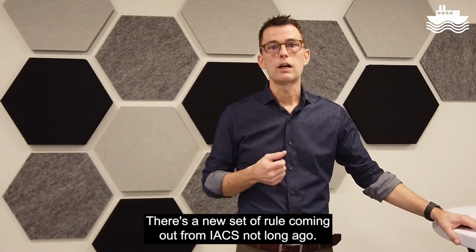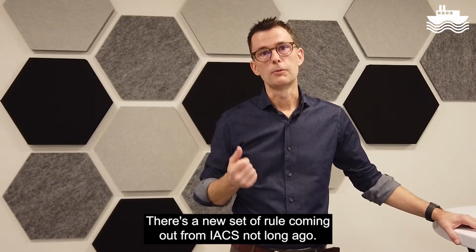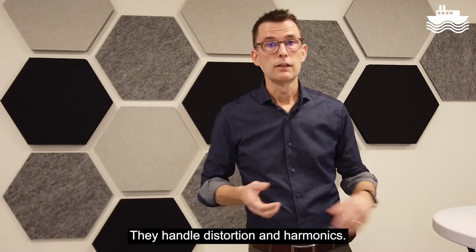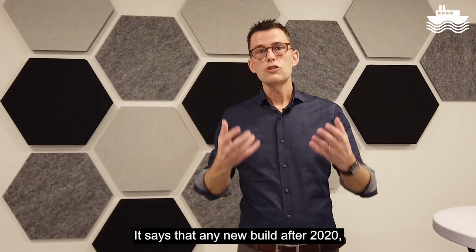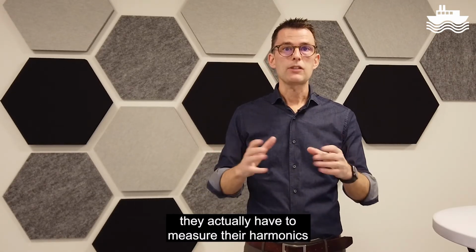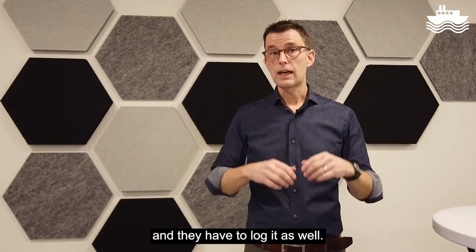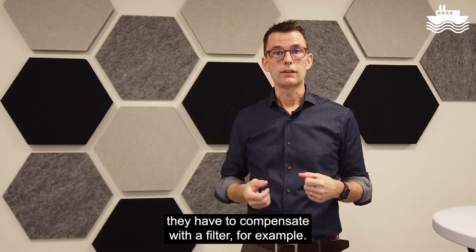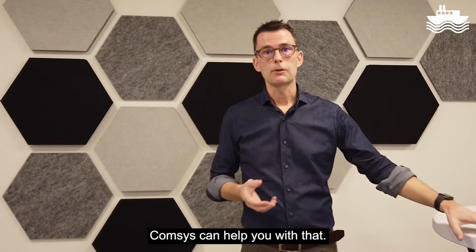There's a new set of rules coming out from IACS not long ago. It's called IACS UR E24. They handle distortion and harmonics. It says that any new build after 2020, they actually have to measure their harmonics and they have to log it as well. Now, in case they exceed the limit, they have to compensate with a filter, for example. Comsys can help you with that.